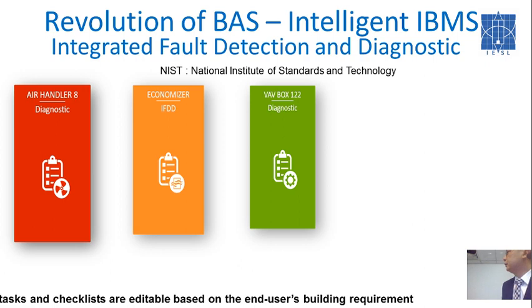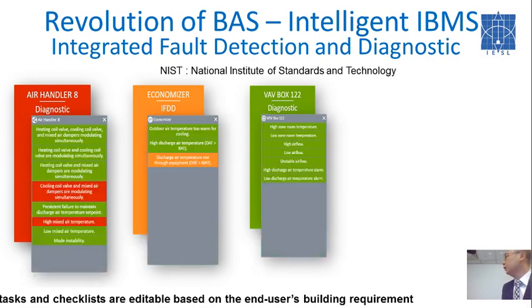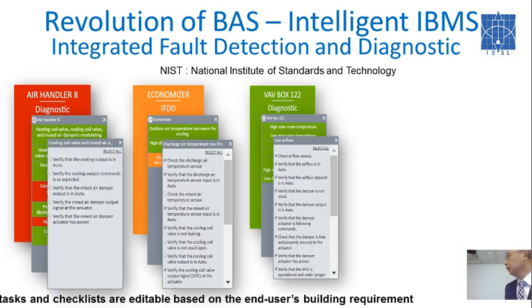These are some examples—air handling units, economizers, VAV boxes. Red indicates a warning within the system. Orange indicates a warning but someone is already working on it. Green means the system is healthy. These are examples of rules we write based on NIST, and each rule has checklists for engineers, technicians, or building owners to check every point and rectify concerns with their equipment. I need to emphasize: the AHU is still working, the blower is still blowing, the valve actuator is still opening and modulating, chilled water is still flowing, you still have comfort in the system—but there's something wrong within the system itself.